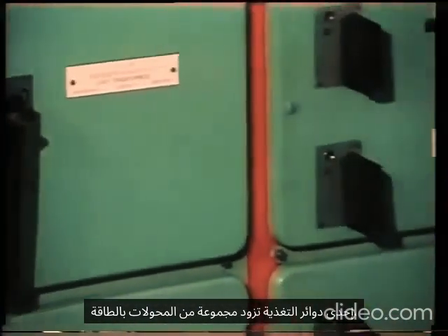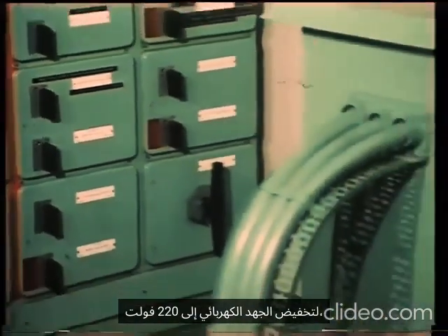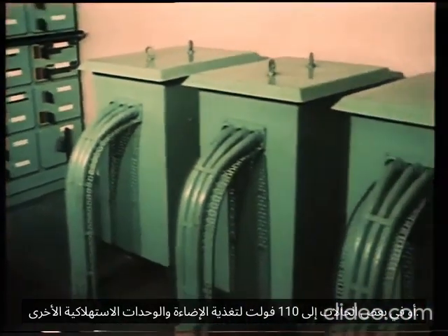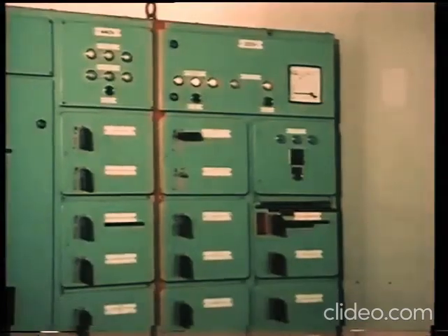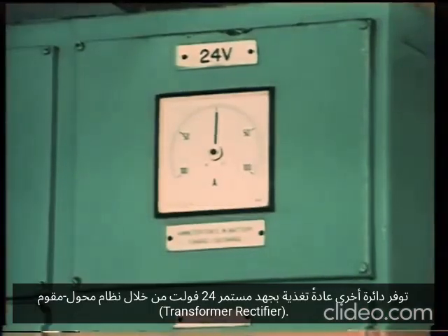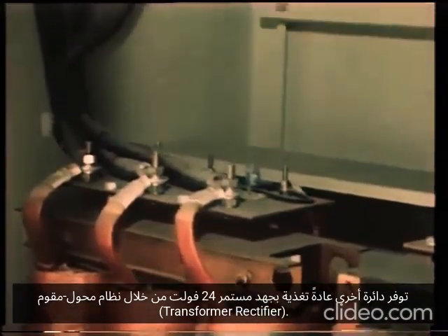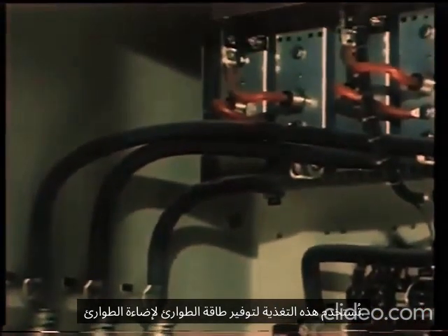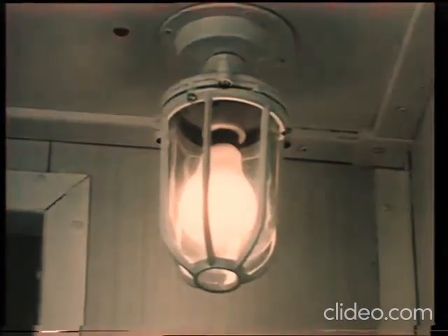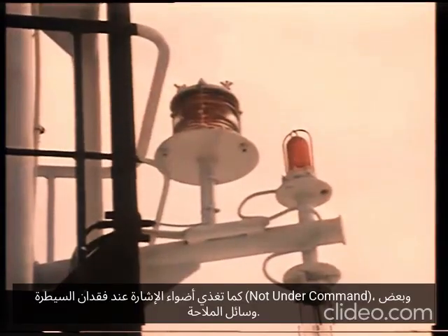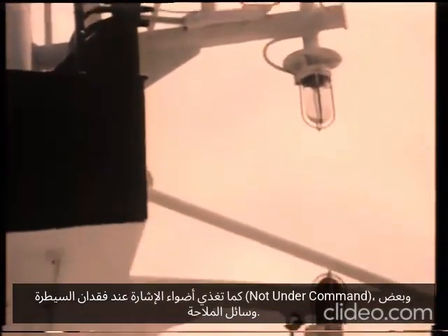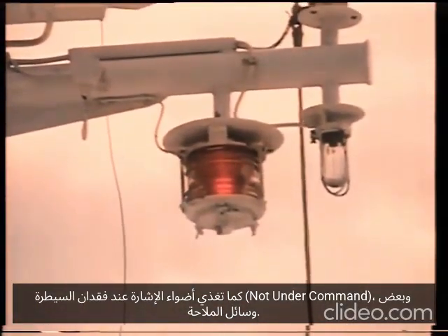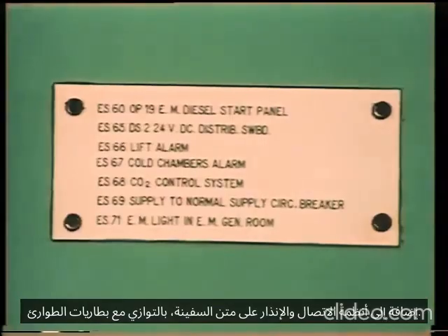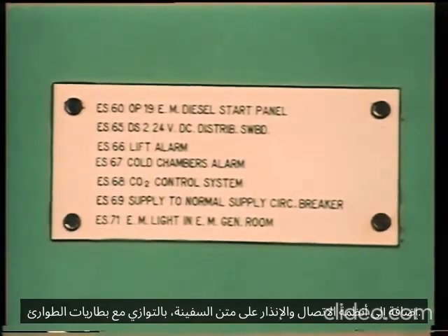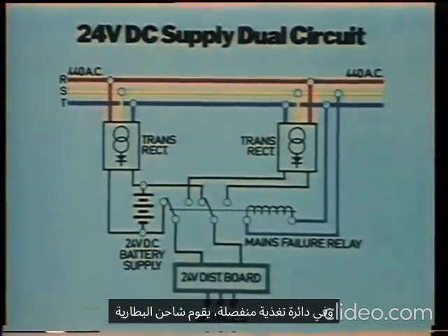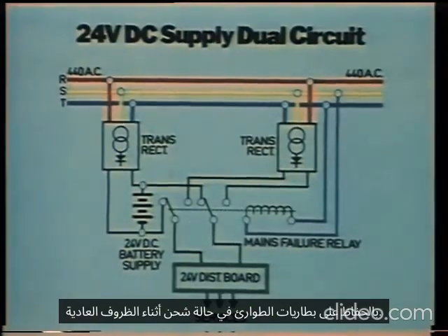One of the feeder circuits supplies a bank of transformers, which reduces the voltage level to 220 volts, or in some cases 110 volts, for lighting and other consumer units. Another circuit provides typically 24-volt DC supply through a transformer rectifier system. This supply provides emergency power for emergency lighting, the not under command signal lights, certain navigation aids, and the communication and alarm systems on board ship, in parallel with the emergency batteries. On a separate feeder circuit, a battery charger keeps the emergency batteries on charge during normal conditions.